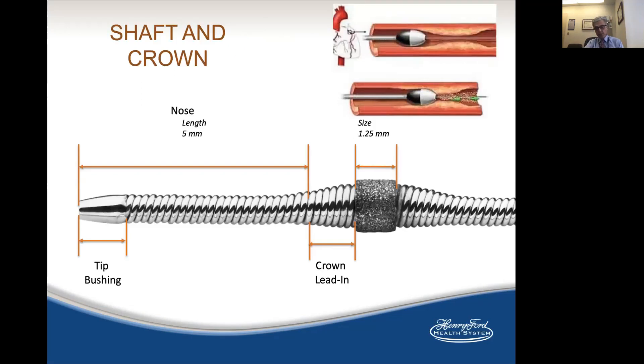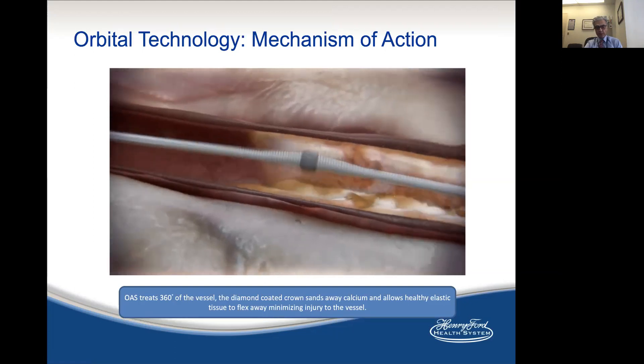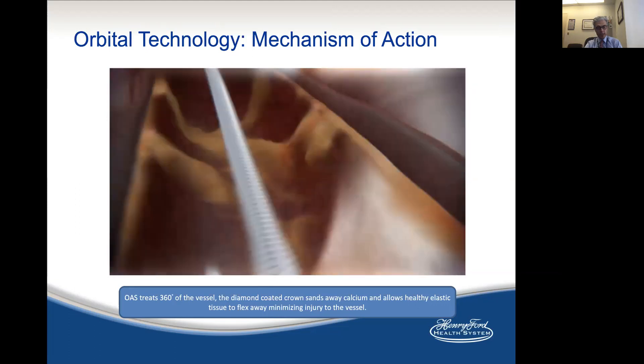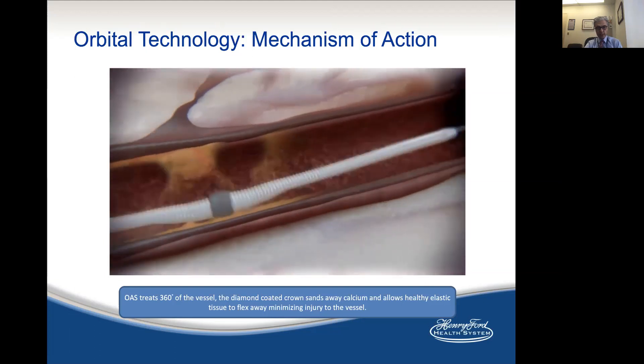This is the crown — the classical crown for coronary orbital atherectomy, size 1.25. The FDA approved the larger size, but this is what's available in the market. If you notice, it has an off-center of gravity. When it rotates at 80,000 or 120,000 RPMs, it will orbit around the vessel. This is different than the front cutting with rotational atherectomy. The orbit will go around the vessel and ablate the calcified plaque, and not damage the non-calcified tissues.